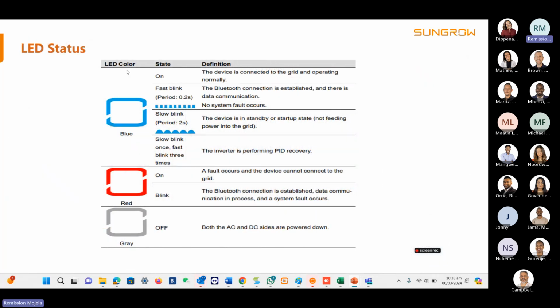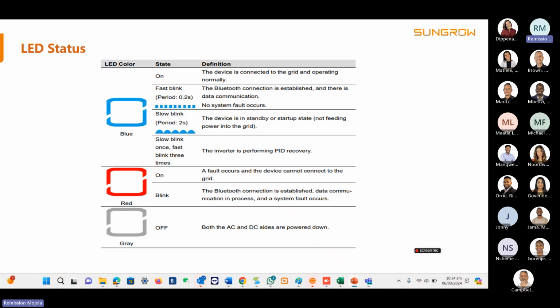And then with the grid ties, if the inverter is solid blue, it means the inverter is actually connected to the grid. But if the inverter is slow blinking, it means that particular inverter is on standby or trying to connect to the grid. But if the light is blinking fast, it just means that the system is connected to a Bluetooth device and is communicating via Bluetooth with another device. And then the red one just means that the inverter has a fault that is preventing the system from starting up. The gray one just means both AC and DC power is actually off.